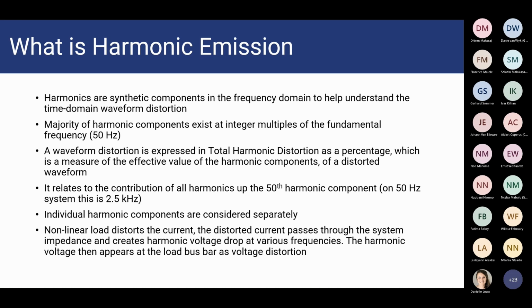In the modern power system, and where we're heading, it's becoming more common that there is also an increase in higher harmonics above the 50th harmonic, caused by inverters that switch at higher frequencies. That's where it becomes important, and where the standard lacks is the assessment and investigation of higher harmonics. It's not at this stage being assessed in the NRS, but it needs to be investigated as well. So THD is one parameter that's assessed, but your individual harmonic components also need to be considered separately. There are also limits specified for individual harmonic components up to the 50th harmonic, depending on your voltage level.